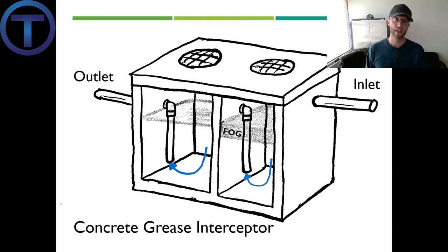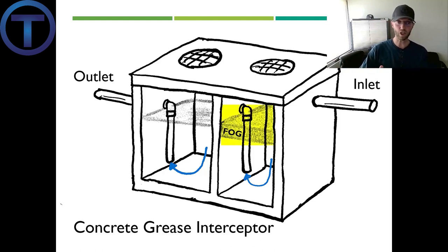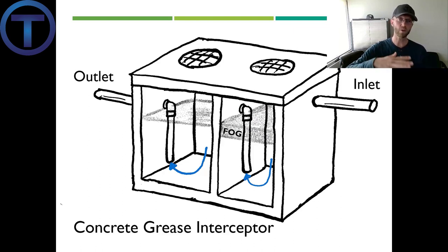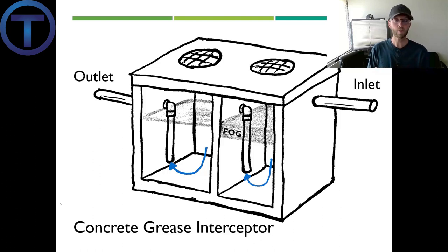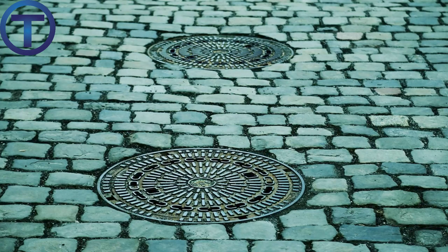Section 1003.3 talks about grease interceptors. For many years, the most basic type was a concrete vault in the ground, as illustrated here. From the inlet, waste goes into the concrete interceptor, and the fats, oils, and grease — that's FOG — float to the top of the first chamber. The rest of the liquid is pushed through to the next chamber, where FOG again floats to the top, and only the liquids pass out the bottom to the outlet. This separates all the grease by gravity. Periodically it has to be cleaned out — there are manholes, and if you drive by a restaurant you'll see two manholes right next to each other, which likely indicates a grease interceptor below ground.